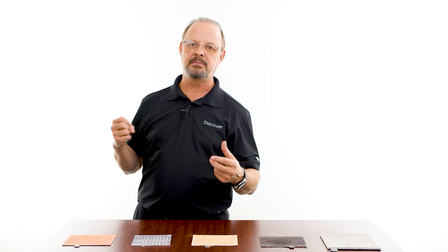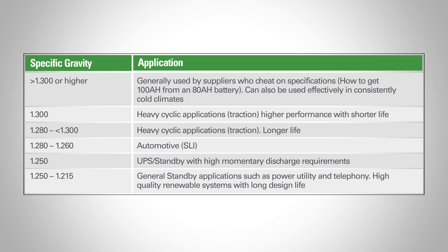However, high specific gravity can also be used effectively in consistently cold climates. For a mission-critical battery bank in the high Arctic or Antarctica, the colder temperatures mean you want to raise the operating temperature of the battery, so higher specific gravity can be used. When adjusted for temperature, the actual battery voltage will be reduced because of the cold.